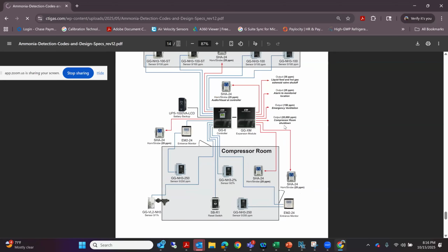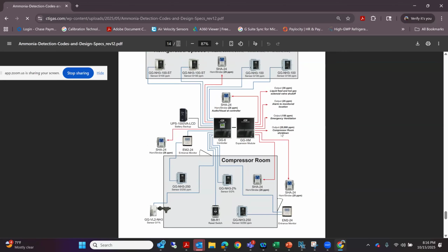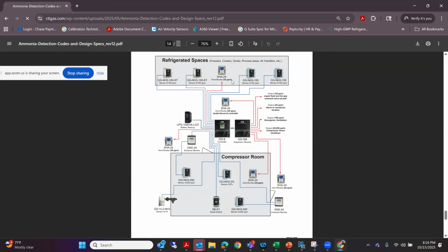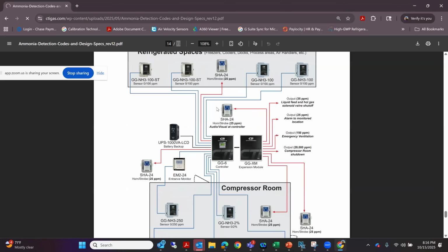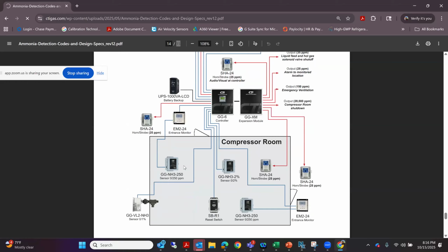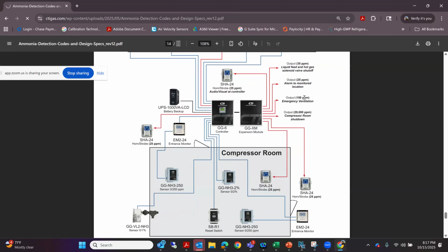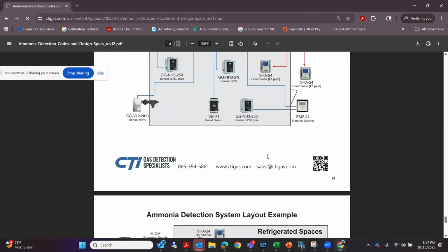And so one of the things that we wanted to show on these drawings is the part numbers and the ranges of the sensors. You can see that this document's real helpful in seeing, okay, well, in the compressor room, we got 2 low-level 0 to 250 range sensors, right? That's going to trip at 25 parts per million. Either one of these sees 25 parts per million, you're going to get your audio visual. And then at 150 parts per million, we're going to do what? We're going to latch on our ventilation output here. So this is some of the output functions that you would expect off the system, along with the e-stop.